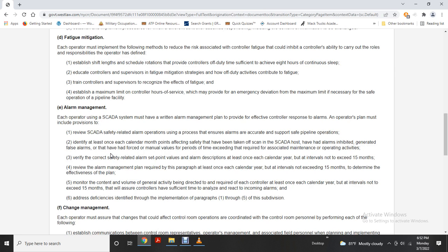Alarm management. Each operator's SCADA system must have a written alarm management plan to provide for effective controller response to alarms. Operators' plans must include provisions to review the SCADA safety-related alarm operations using a process that ensures alarms are accurate and support safe pipeline operation. Identify at least once each calendar month points affecting safety that have been taken off scan in the SCADA host. Have alarms inhibited, generated false alarms, or had forced manual values for a period of time extending beyond the required associated manual maintenance operating activities.